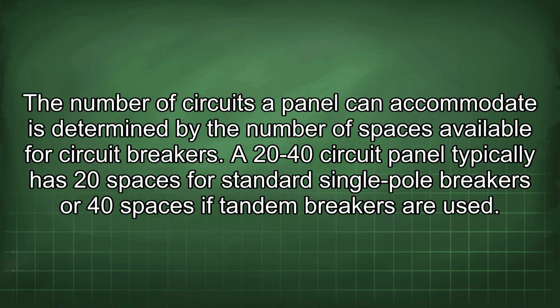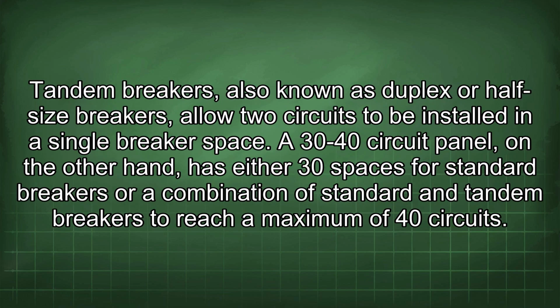A 20-40 circuit panel typically has 20 spaces for standard single-pole breakers or 40 spaces if tandem breakers are used. Tandem breakers, also known as duplex or half-size breakers, allow two circuits to be installed in a single breaker space. A 30-40 circuit panel, on the other hand, has either 30 spaces for standard breakers or a combination of standard and tandem breakers to reach a maximum of 40 circuits.